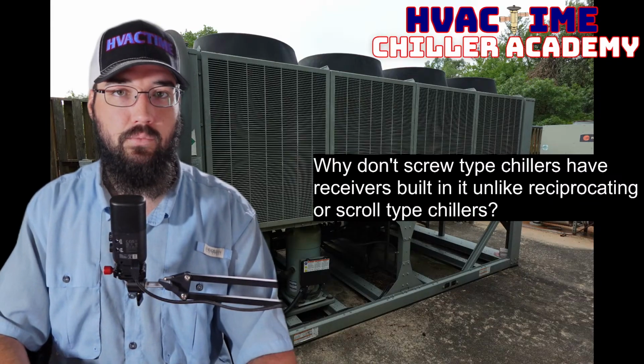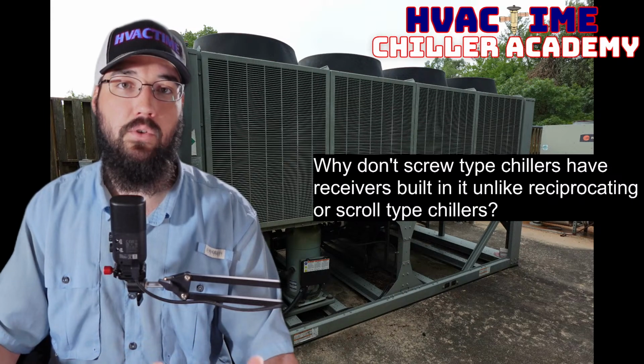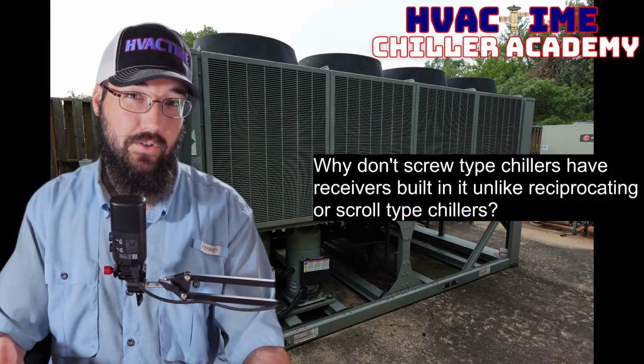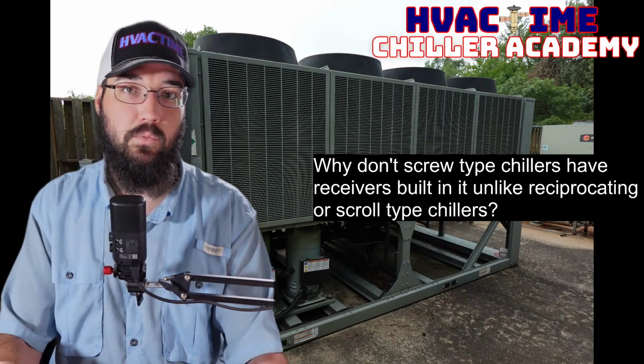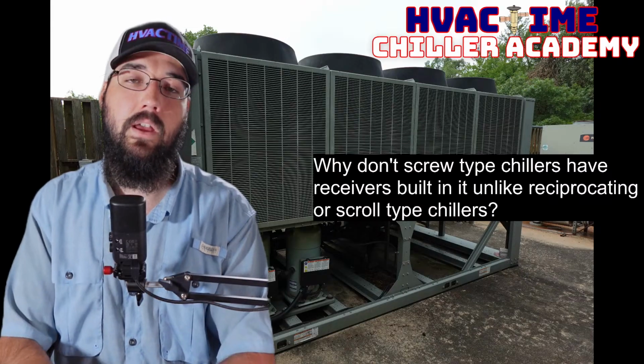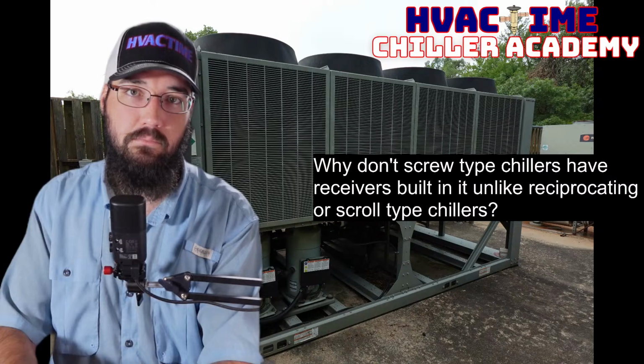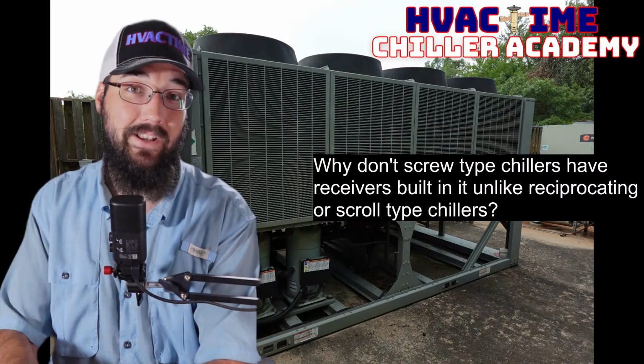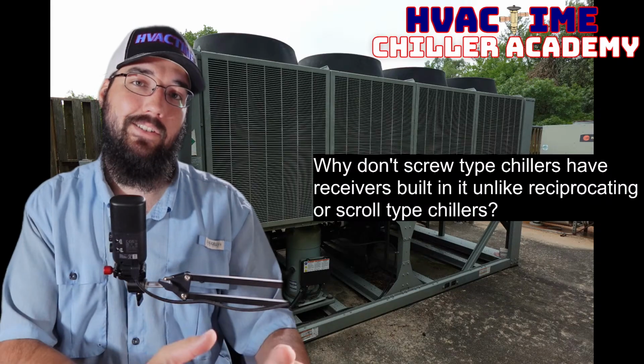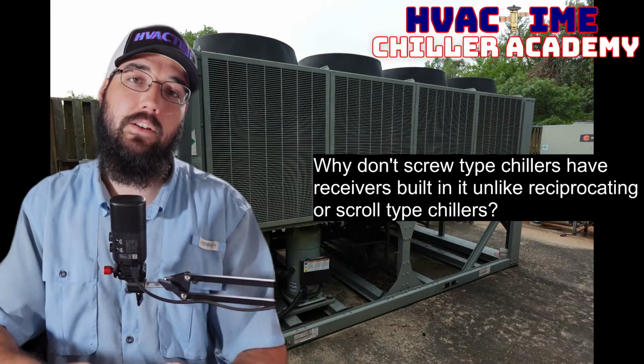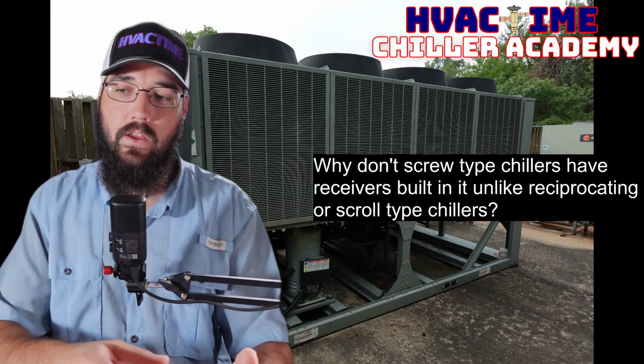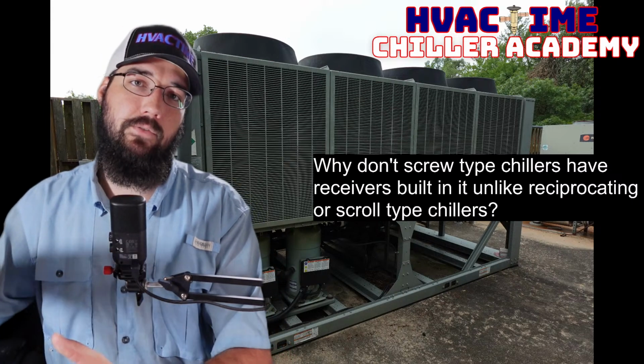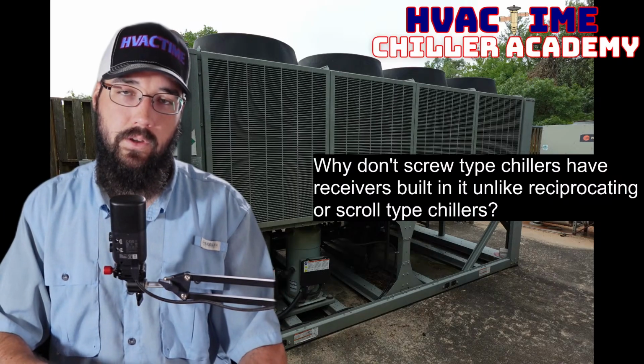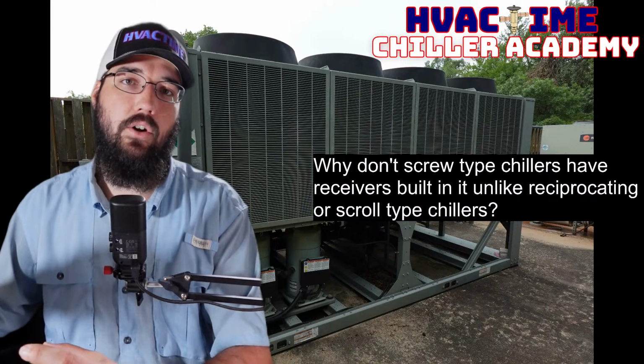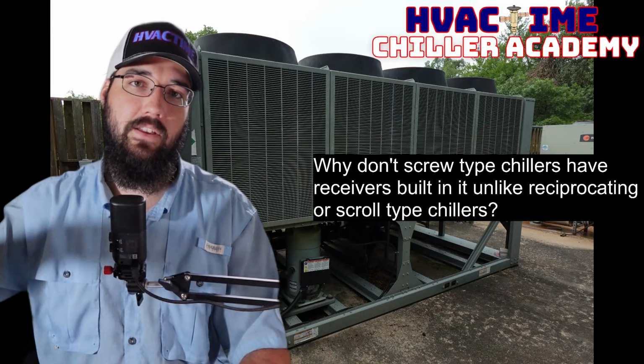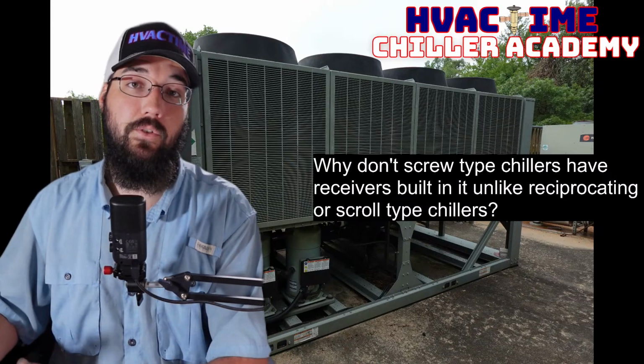That's something that, like with a scroll machine, unless we have multiple compressors, we don't have the ability to do. And I would venture to say that if I'm right about you seeing this in more specialty, like process cooling applications, then you're probably only seeing one, maybe large compressor, but just one compressor, and it may not really have much in the way of unloading ability. But that is not true when we get into these other types of compressors. We have the ability to unload quite heavily in most cases. So that helps compensate for when we start to reduce load, we have the ability to regulate our flow much better, and we don't need the ability to stack that liquid refrigerant somewhere the same way we do with these other types of systems.